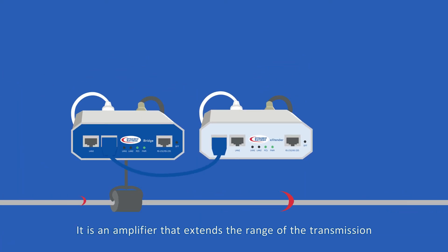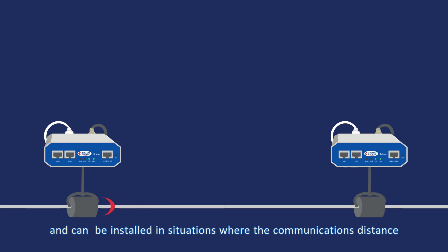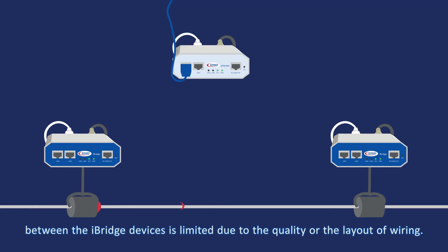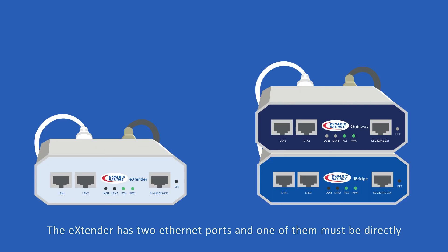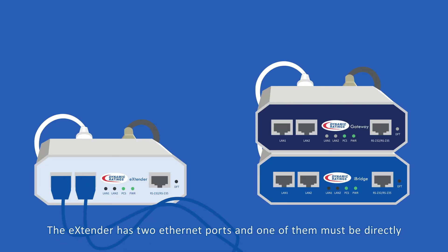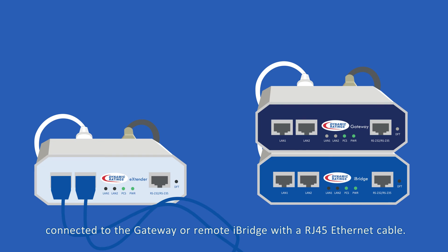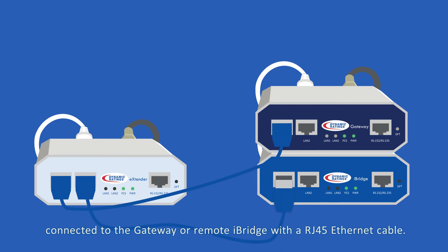The extender is an amplifier that extends the range of the transmission and can be installed in situations where the communications distance between the iBridge devices is limited due to the quality or the layout of wiring. The extender has two Ethernet ports, and one of them must be directly connected to the gateway or remote iBridge with an RJ45 Ethernet cable.